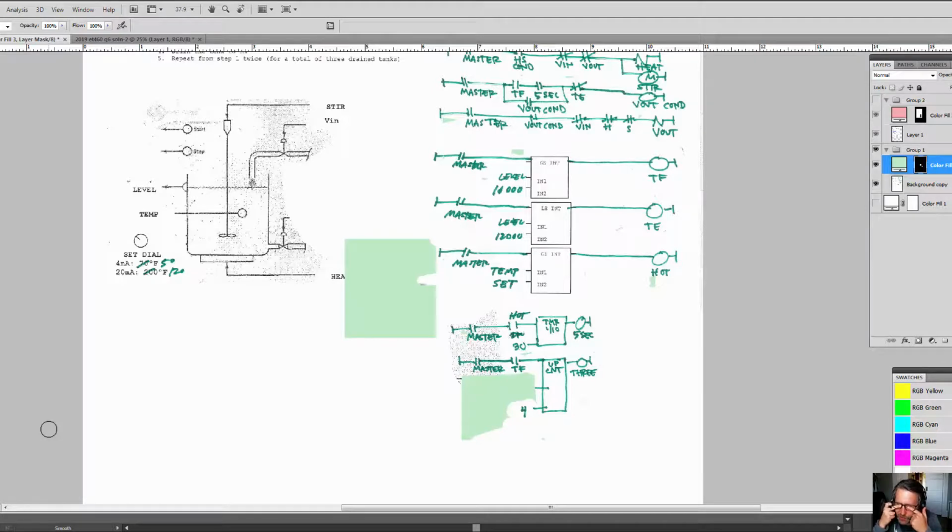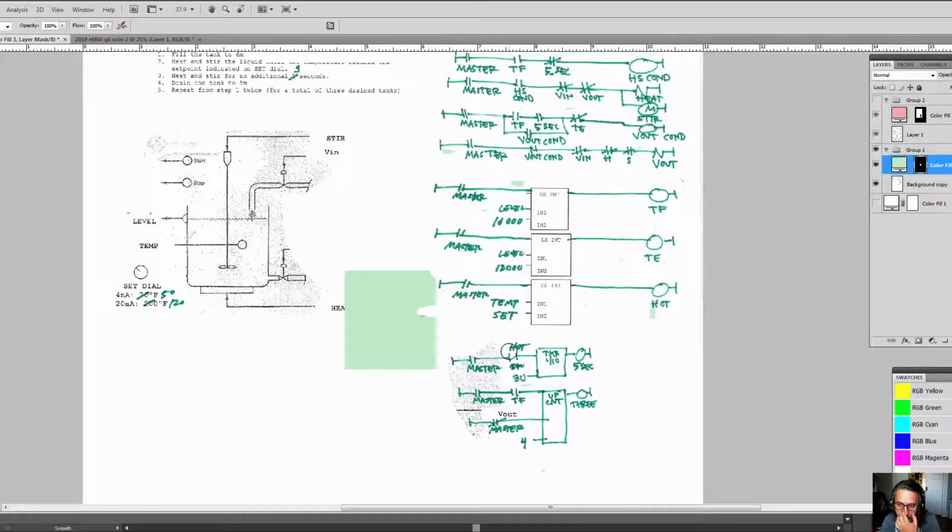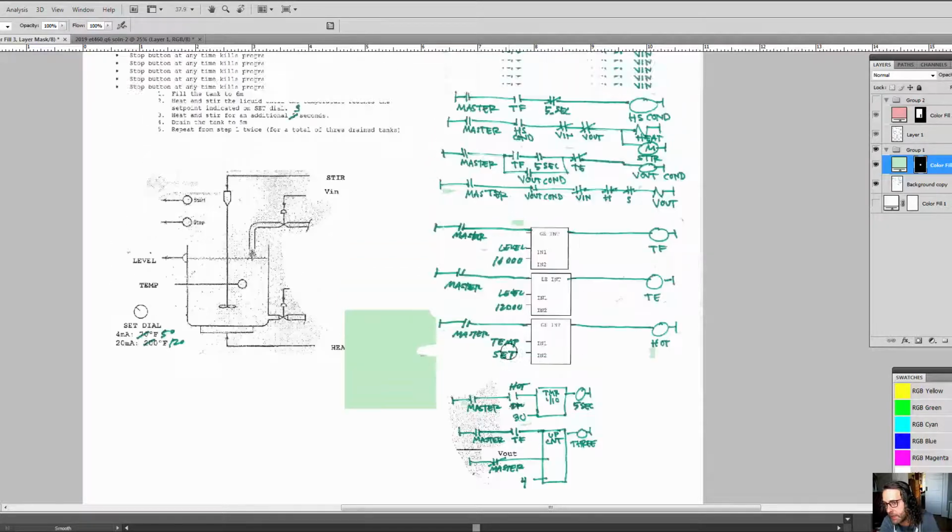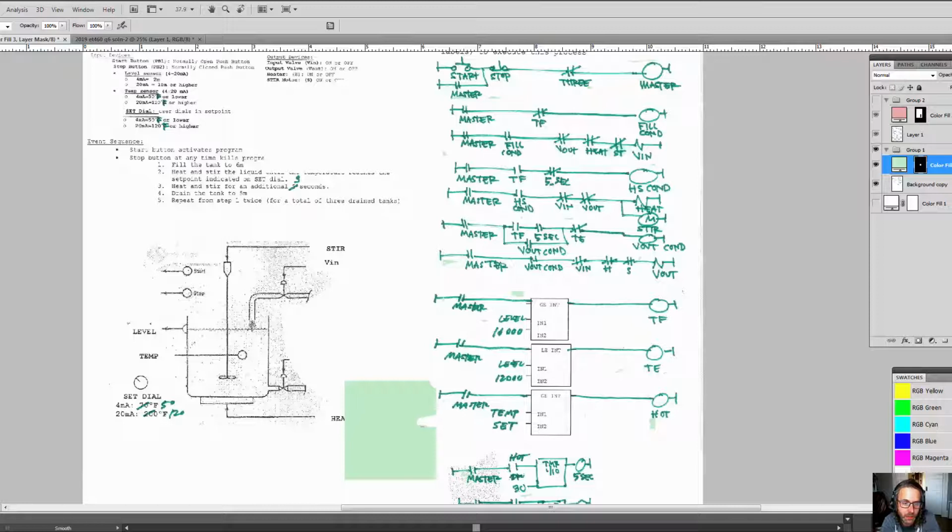So it's going to fill and drain for 1, fill for number 2 and drain, fill for number 3 and drain. It's going to fill that 4th time. And then the program will click off. So it's going to end with a full tank. But that's totally fine. And I'm going to reset this with a normally closed master, meaning that when the program deactivates, then you reset your counter. All right, so did you get that one?